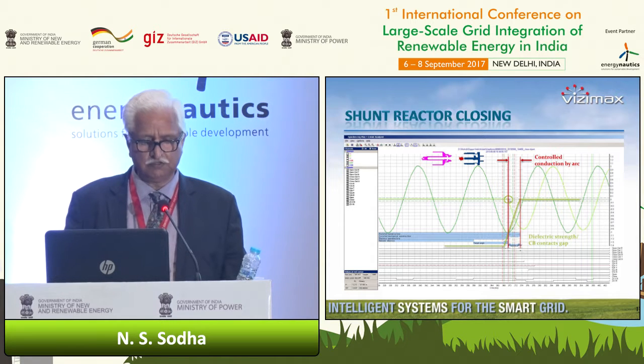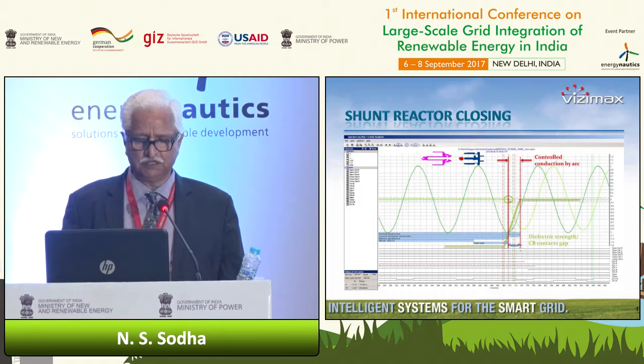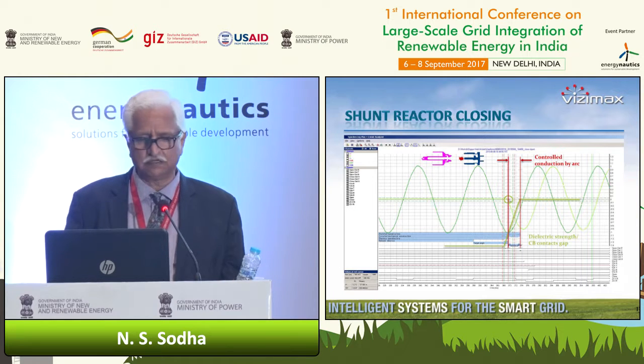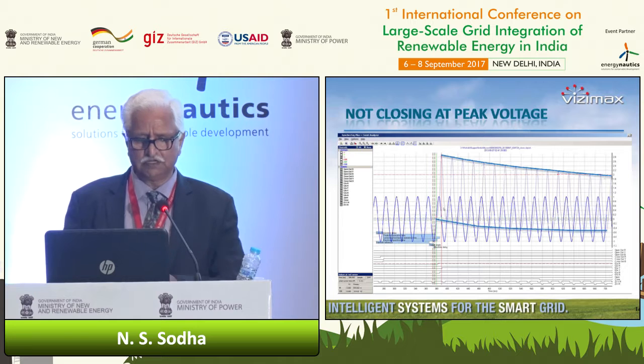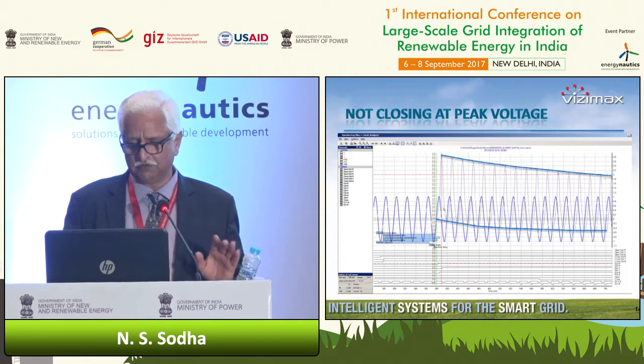This is a shunt reactor closing. Also, we have observed that the shunt reactor closing is a very onerous duty on the breaker, and you can see here the physical movement of the contacts. You can see here the contact is moving, the arc is struck between the contacts, and then when it is fully closed, then the waveform is improving. So basically it's the operation in the closed form, then it is opening, and then it is the beginning. So the closing operation is done like this, and the system starts measuring at the time of strike of the arc, and when the contacts are coming closer to each other. In the fully closed position, the switching operation will be done. And when not closing at the peak voltage, the voltage deviations will be observed, and we can see that the situation can improve if you put the control switching and the proper instant of breaker closing is decided.